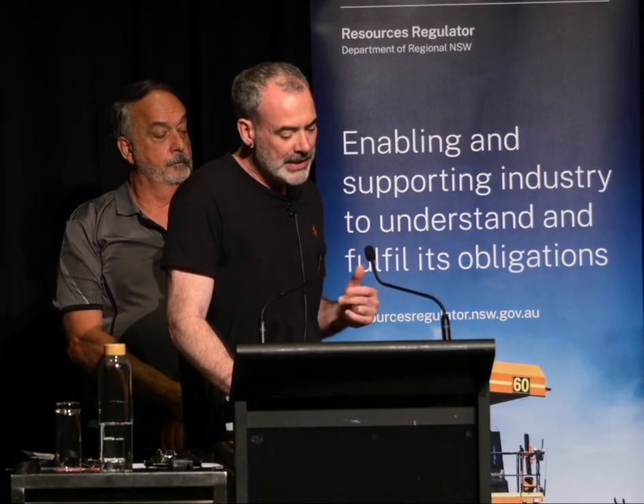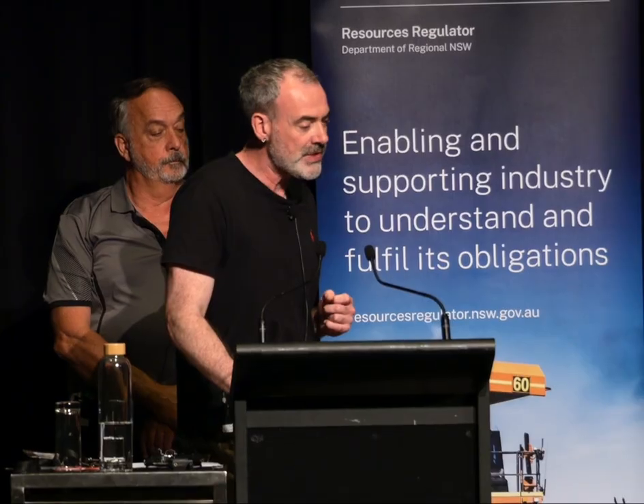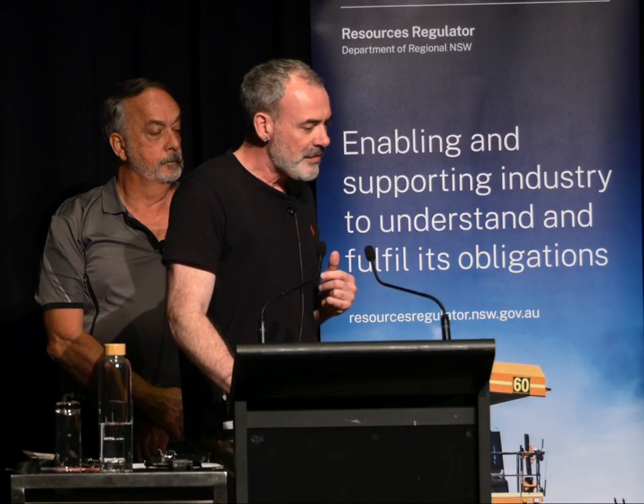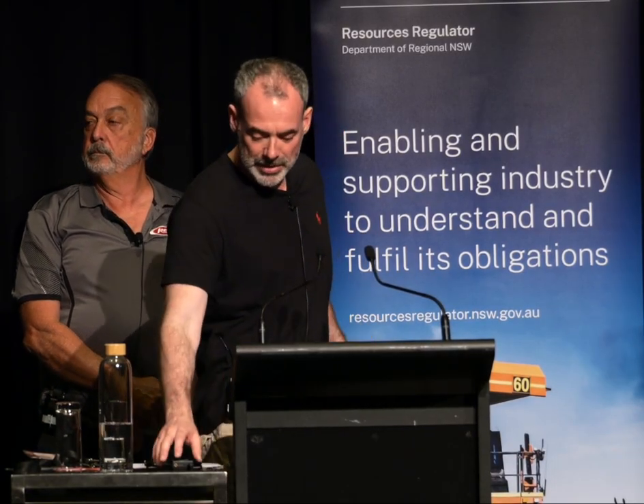And along with mineral oil, silicone oil, natural and synthetic esters are used in transformers as a dielectric fluid. And the role of these dielectric fluids is to be an electrical insulator. They're part of the transformer cooling system, so they distribute heat from the core and the windings, which is important for the preservation of the paper insulation. When the paper's at end of life, the transformer needs to be replaced or rewound. They enhance the dielectric properties of the paper insulation, and also they are a store of diagnostic information that you can access via sampling and testing in the lab.